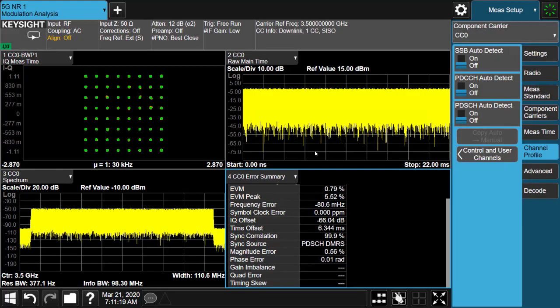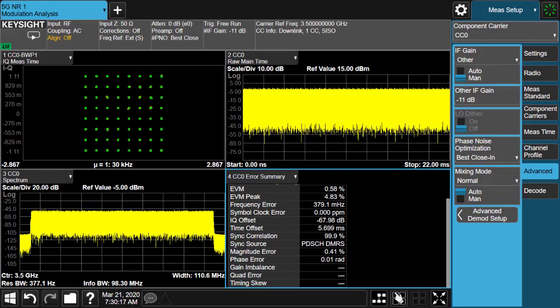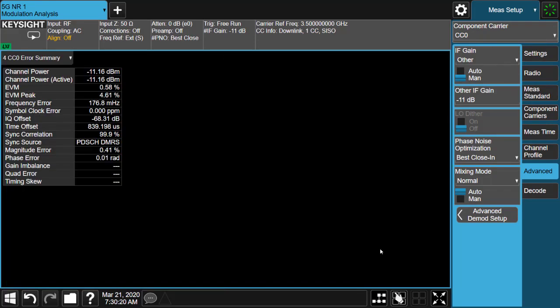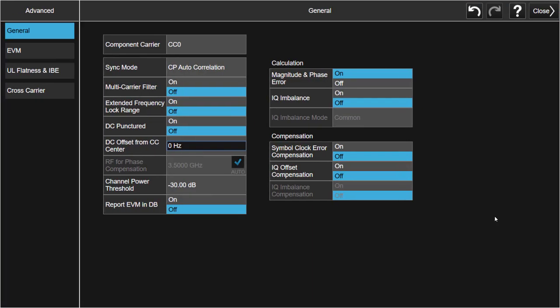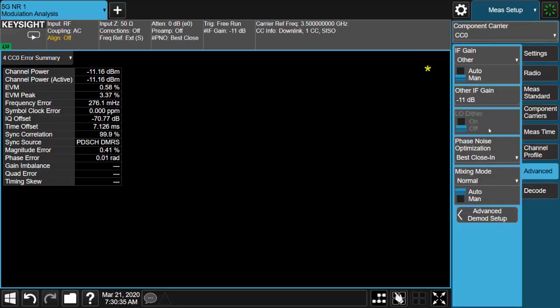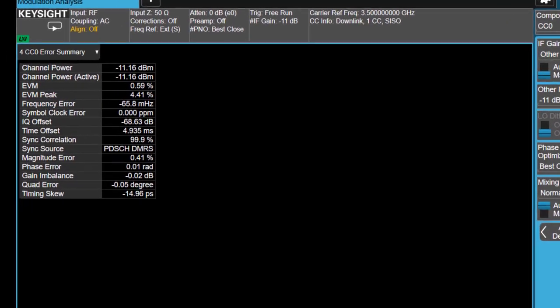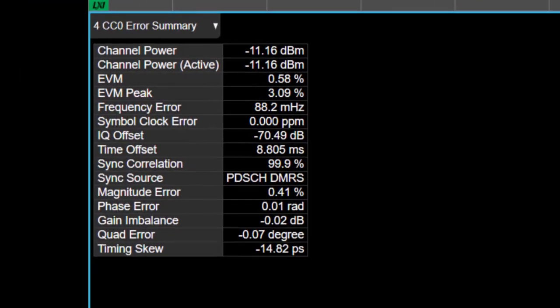Some new metrics have been added to the error summary table. That includes timing skew, gain imbalance, quadrature error, magnitude error, and phase error. User can enable the calculation for those metrics under advanced demod setups menu, and then view the results.